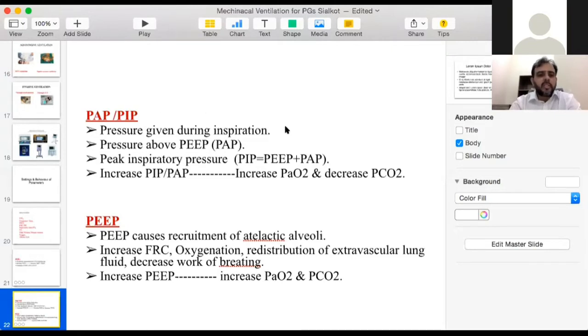So this is the maximum pressure achieved during inspiration. We can control it through one knob by giving pressure. So PEEP, what is PEEP? PEEP is the pressure that is maintained throughout the respiration. During inspiration and expiration, the airways are slightly distended. Normally, the PEEP is between 3 to 4, but we can increase the PEEP. What is the benefit? If you increase the PEEP, all the airways, from the upper airways to the lower airways to the alveoli, will be distended. They will be inflated slightly. The inflation will improve oxygenation as well as delivery of air down the airways. If you maintain a small amount of pressure during expiration, it will prevent collapse of the alveoli during expiration, so that they can be easily inflated again during inspiration.